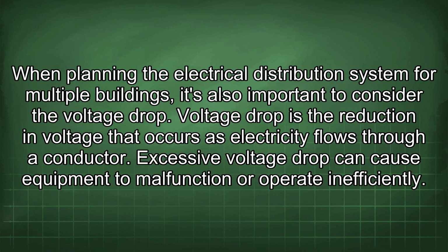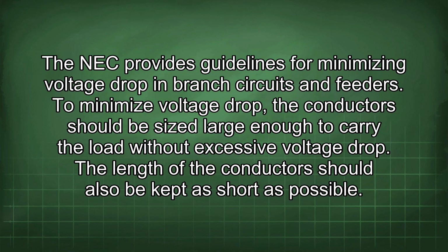When planning the electrical distribution system for multiple buildings, it's also important to consider the voltage drop. Voltage drop is the reduction in voltage that occurs as electricity flows through a conductor. Excessive voltage drop can cause equipment to malfunction or operate inefficiently. The NEC provides guidelines for minimizing voltage drop in branch circuits and feeders. To minimize voltage drop, the conductors should be sized large enough to carry the load without excessive voltage drop. The length of the conductors should also be kept as short as possible.